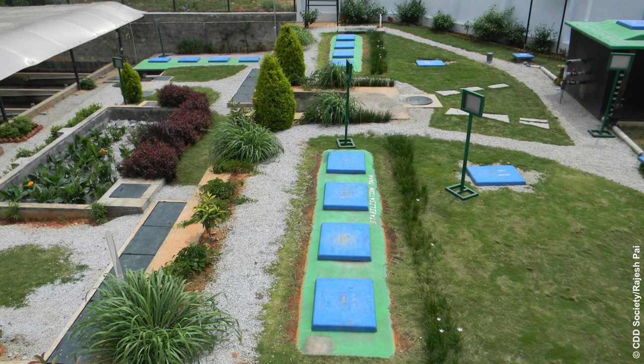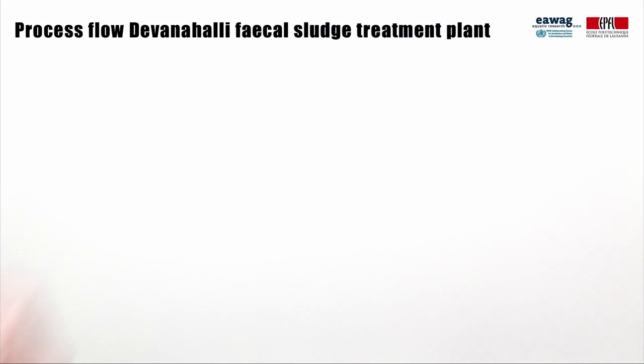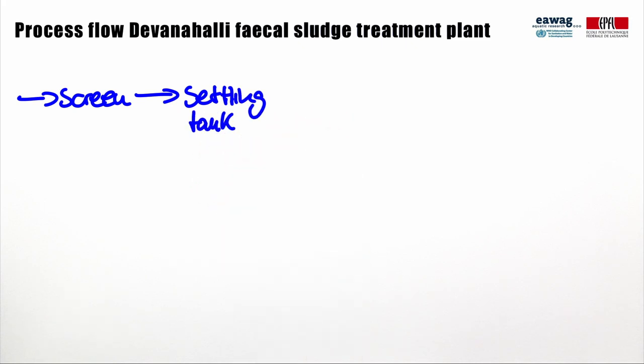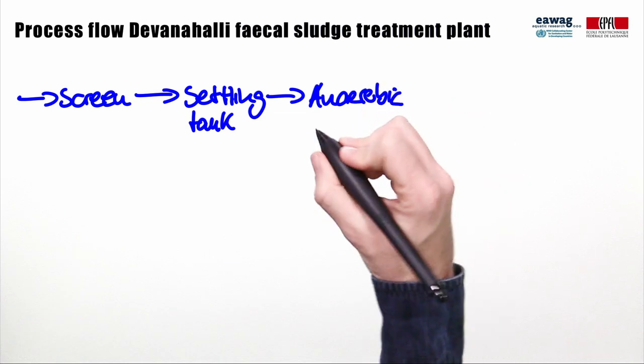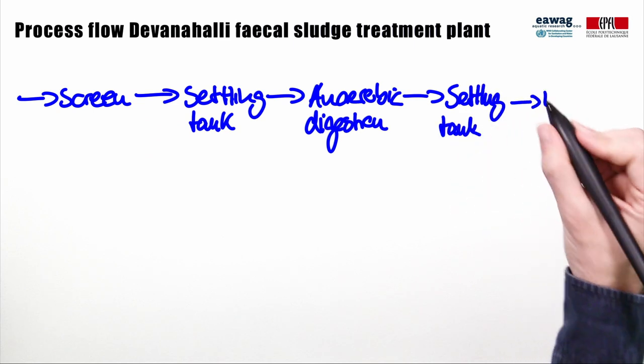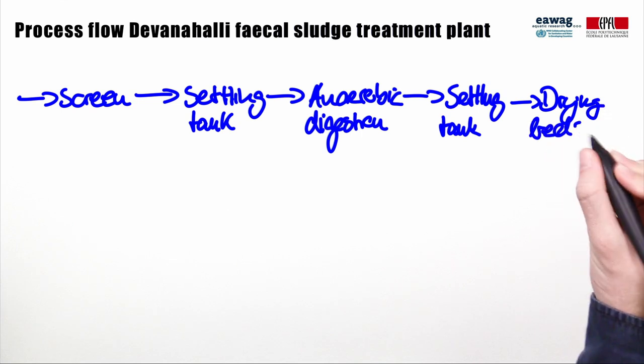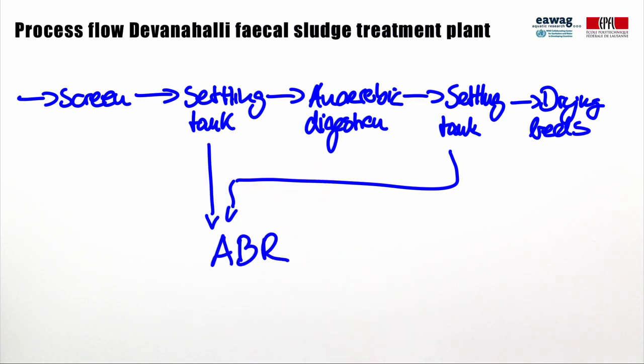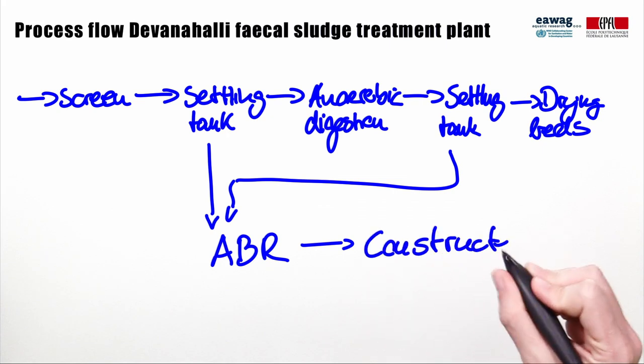This picture shows the fecal sludge treatment plant in Devanahalli, north of Bangalore in India. In contrast to Demagete, Devanahalli has a treatment capacity of only 6 cubic meters per day and receives mostly sludge from pit latrines. This is one reason why different treatment technologies were selected for effluent treatment. Following a screen, solids and liquid are separated by a settling tank. The solids are treated in parallel by anaerobic digesters, followed by another settling tank, after which solids are dewatered on unplanted drying beds. Instead of waste stabilization ponds, the liquid effluent from the settling tanks is treated in an anaerobic baffled reactor (ABR), followed by treatment in constructed wetlands.